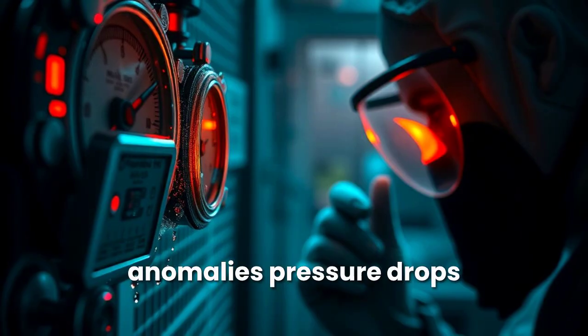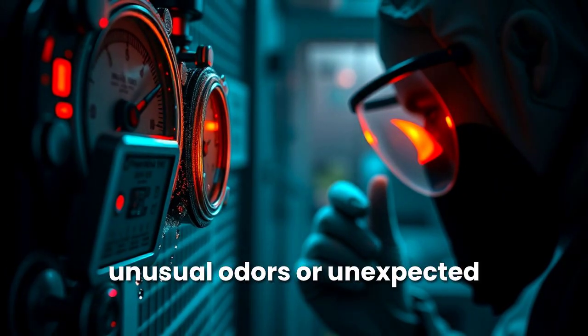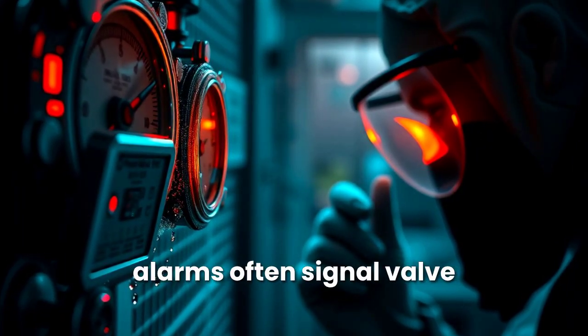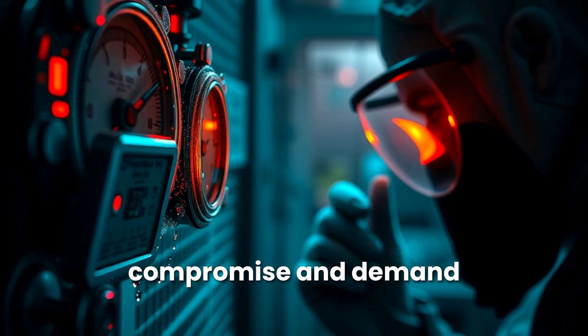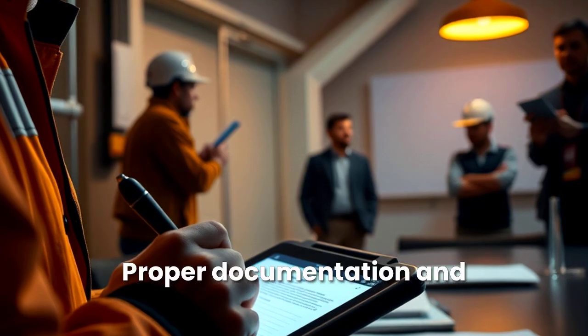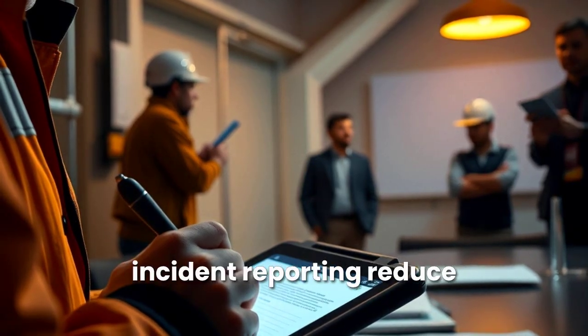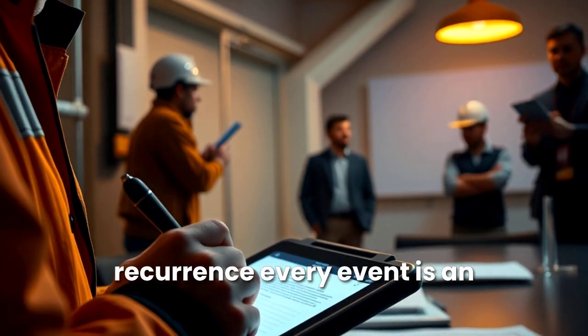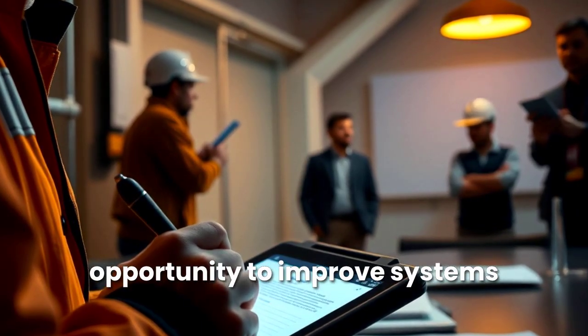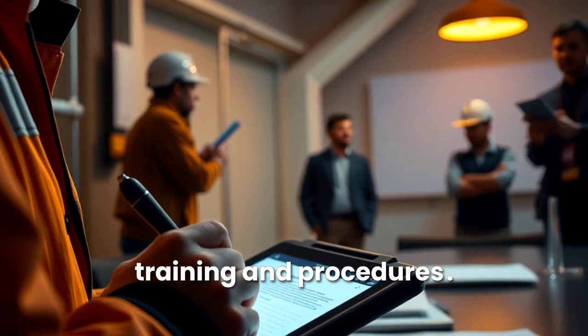Flow anomalies, pressure drops, unusual odors, or unexpected alarms often signal valve compromise and demand immediate verification. Proper documentation and incident reporting reduce recurrence. Every event is an opportunity to improve systems, training, and procedures.